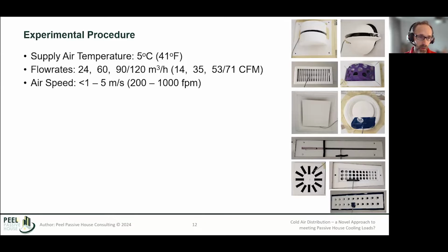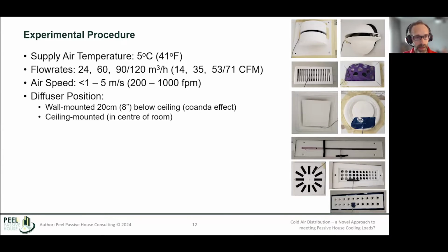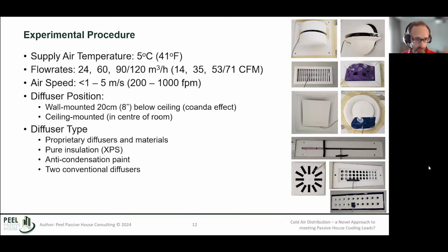We also looked at airspeed ranging from about 200 to 1,000 feet per minute, and different diffuser positions. We looked at wall mounted, about 8 inches below the ceiling. Anyone familiar with the Coanda effect knows that kind of induction along the ceiling. We tried to take advantage of that, as well as using a ceiling mounted position for the diffusers as a reference.